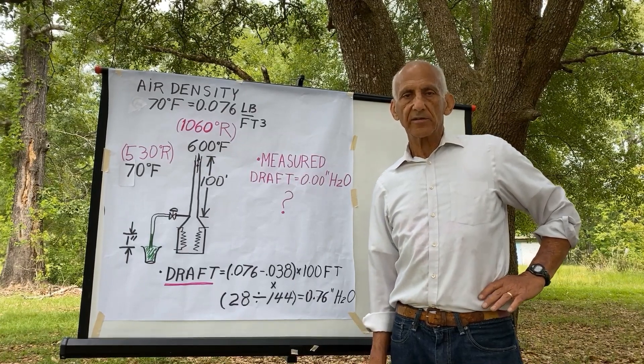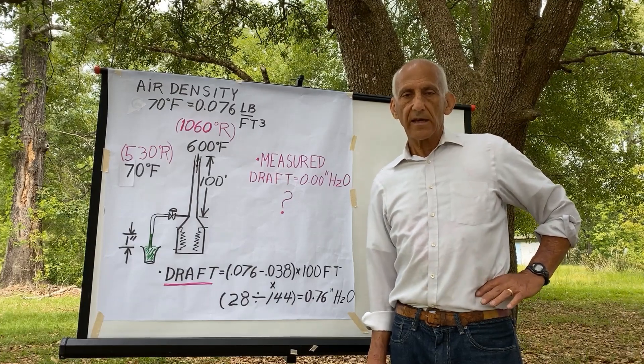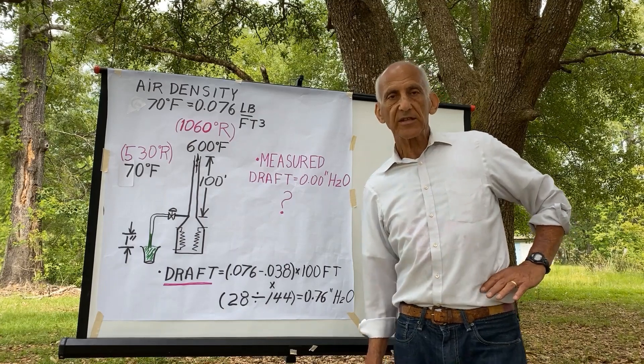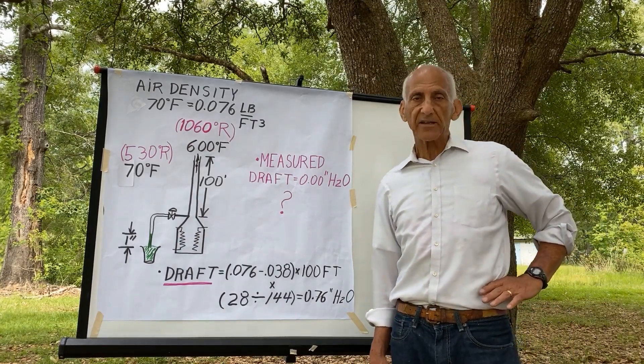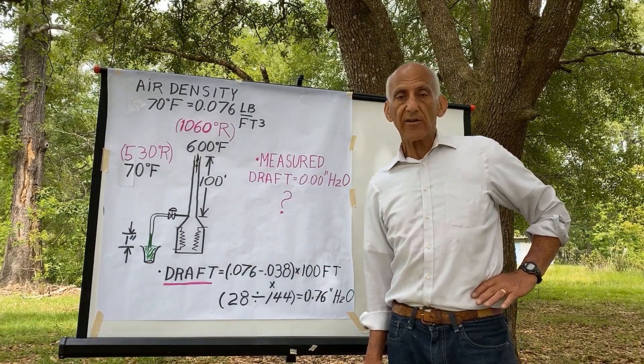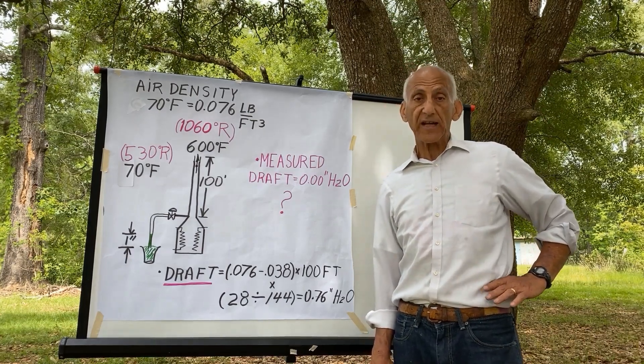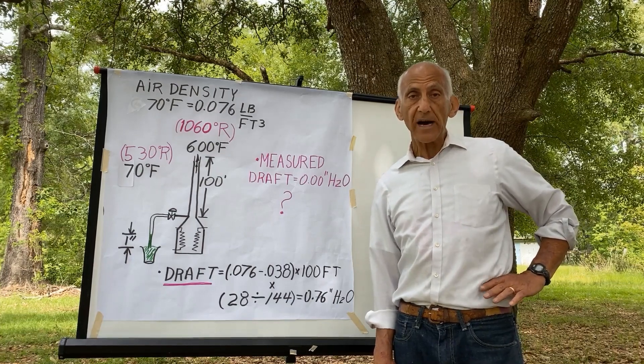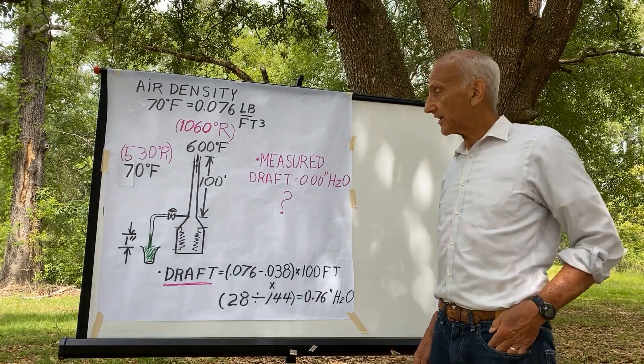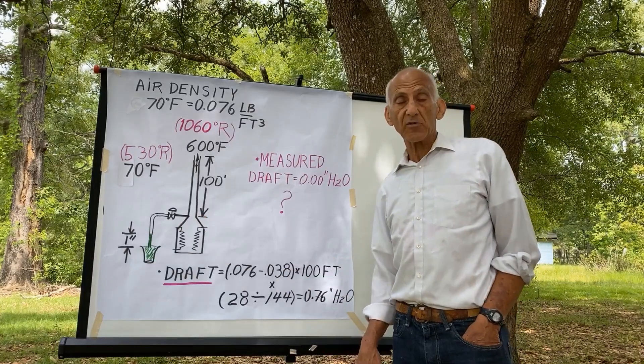I was teaching a seminar in Cartagena, Colombia, in South America, and one of the students came over to me after one of the sessions and said, 'Mr. Liebman, we'd like to have you review a letter we're writing to Foster Wheeler. We need them to review our calculation procedure to calculate the draft we're developing in our crude heater below the bottom row of convective tubes.